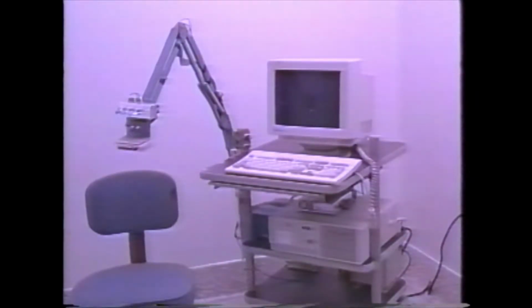Separate transducers for measurements of flow, mouth pressure, esophageal pressure, and gastric pressure are also placed close to the EMG amplifier on the lever. The amplified EMG signals are analog to digitally converted and acquired into a personal computer at a sampling rate of 2000 Hz per channel. Flow, pressure, and other mechanical signals are converted by a separate A to D board and are acquired at 100 Hz. For patient protection, all electrical units are connected to the mains via a super isolation transformer.